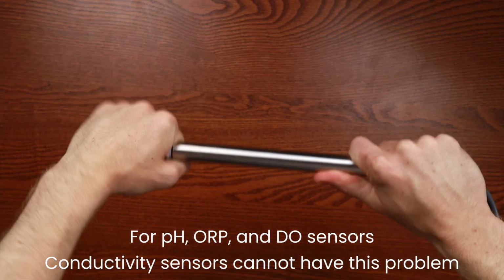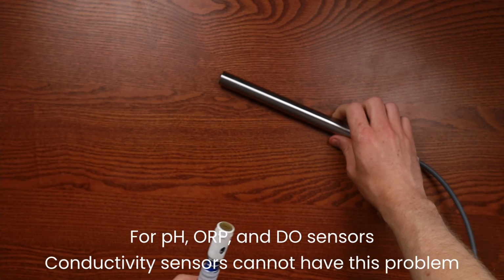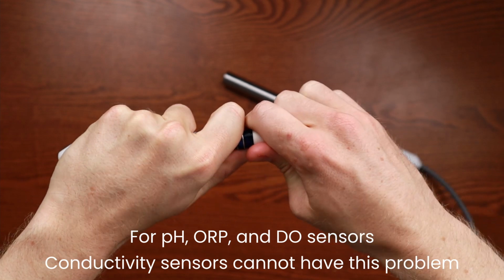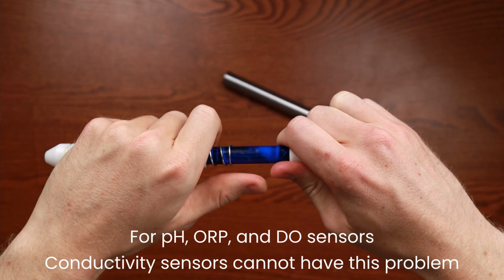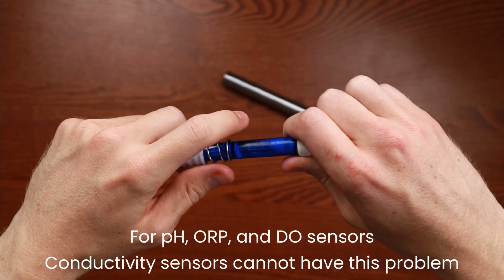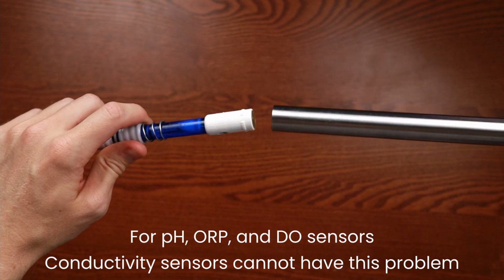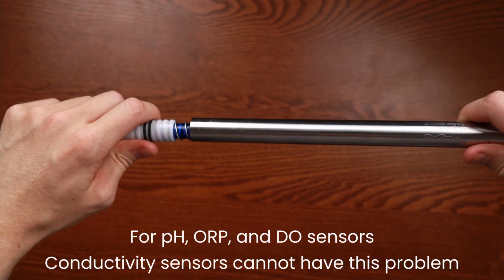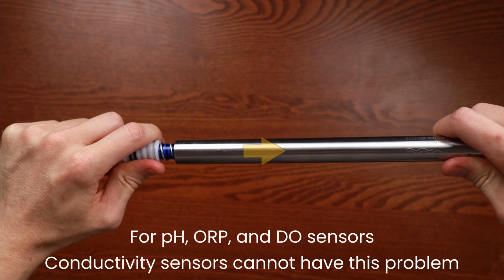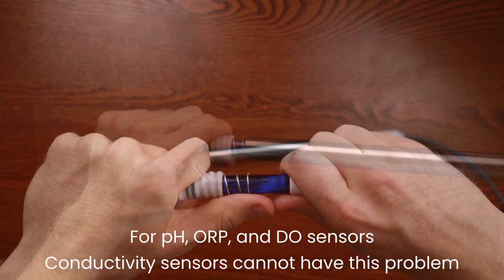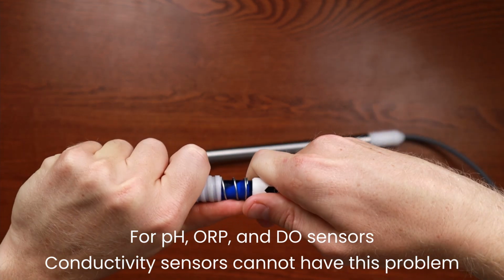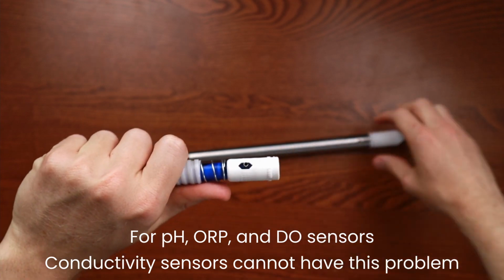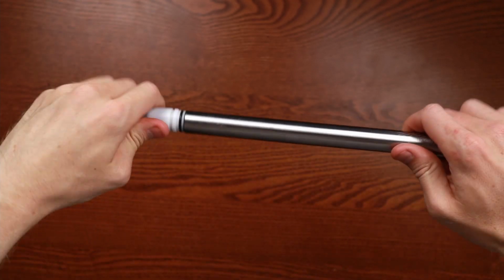To fix this, unscrew the electrode body and pull out the electrode. Gently rotate and pull until the electrode releases. Leave the loose electrode resting in the electrode body and use it to push the circuit board up to contact the cable connector. Do not twist the electrode while doing so, as this could damage the circuit board connector. Reinsert the electrode to the proper depth and screw back into the housing. Retest the sensor and confirm that it is reading properly.